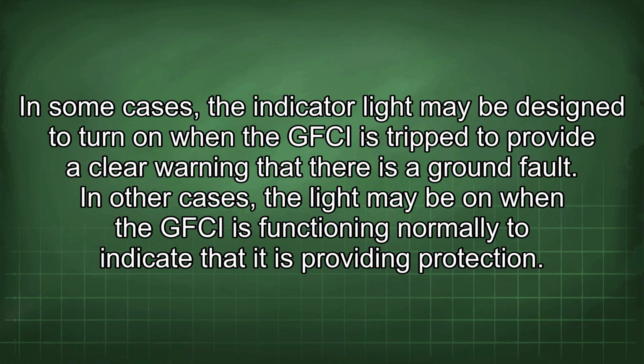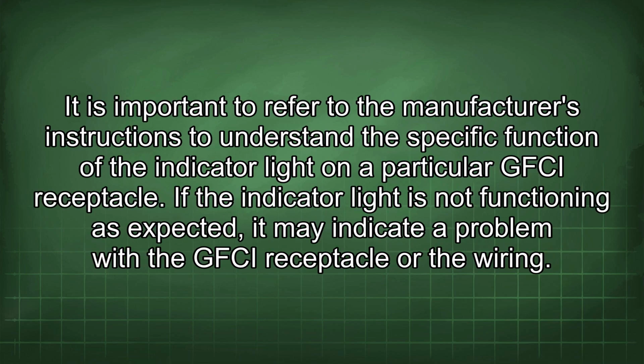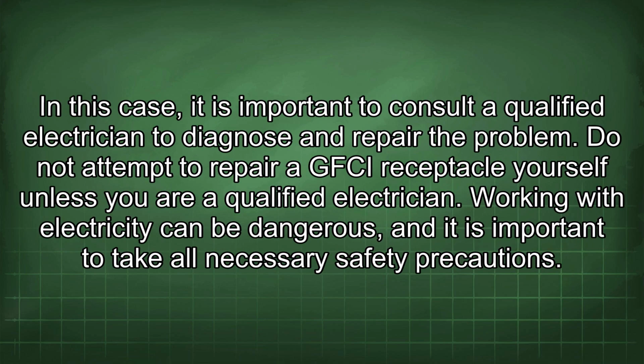In other cases, the light may be on when the GFCI is functioning normally to indicate that it is providing protection. It is important to refer to the manufacturer's instructions to understand the specific function of the indicator light on a particular GFCI receptacle. If the indicator light is not functioning as expected, it may indicate a problem with the GFCI receptacle or the wiring. In this case, it is important to consult a qualified electrician to diagnose and repair the problem.